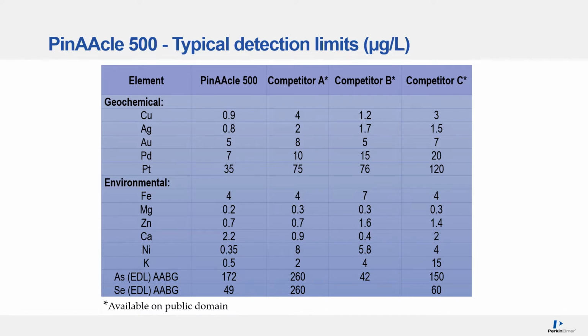The other benefit of the PinAAcle 500, when we take into account the new optical system, the solid-state detector, and all the other optimizations, is that this leads you to better detection limits overall. So we can look at some selected elements here and compare it to different competitors with what they've shown as results publicly available in application notes. The PinAAcle 500 has the same or better detection limits across a wide range of elements. So this just shows that the system definitely has been optimized optically for superior performance.